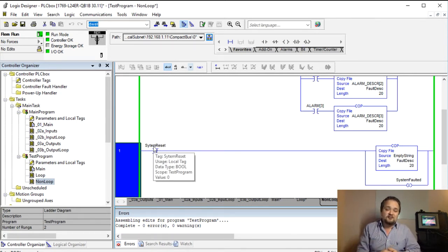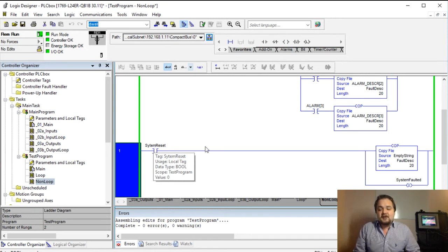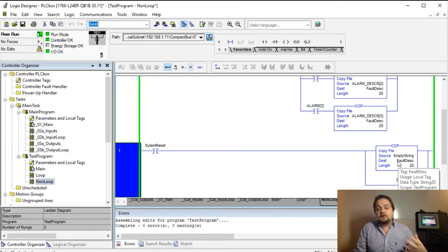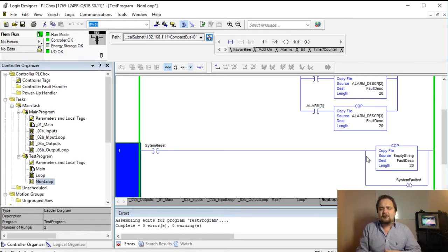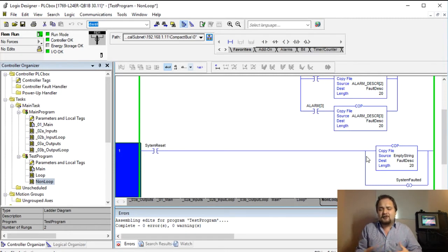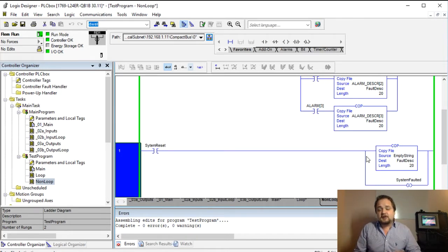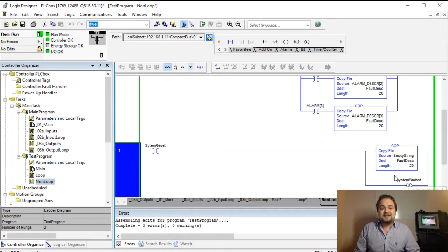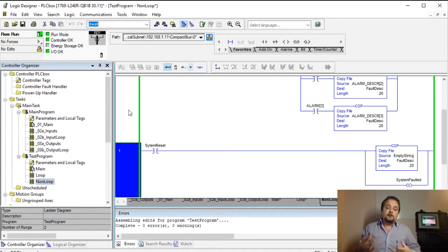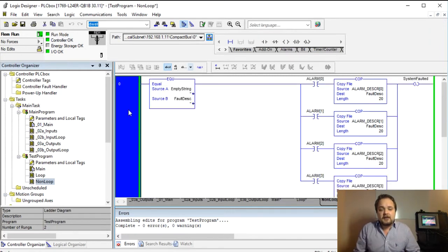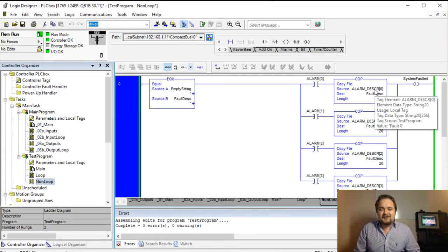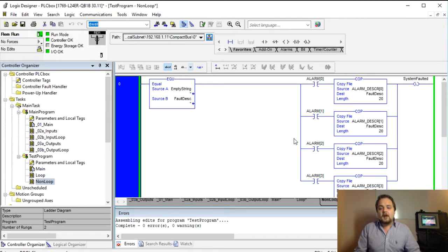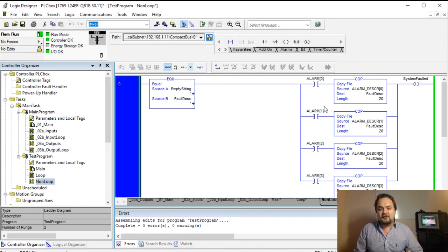So you hit a system reset, the empty string which once again contains absolutely nothing, it gets copied back into the fault description and of course you need to set up ways that you check for you know if the alarm is still present or it's been cleared by somebody else. So this is not a full implementation of a system but it's essentially a way to capture alarms. And a system fault bit is unlatched in order to make sure that the system is not faulted and at that point you know you could start the machine for example. So the way this works is first of all I have different descriptions so all it is is just fault zero, fault one, fault two and so on but essentially you'd give it a meaningful description.